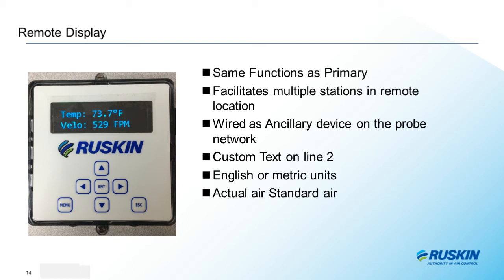Two lines of the display can be configured. Actually, line 2 of the display can be configured with custom text, such that where it says VELO in this screen shown here, you can edit that and have it read AHU1 or RTU3 or any custom text you want to see. Configuration options support both metric and English units and can be set to display either actual airflow or standard airflow, adjusting for both altitude and humidity when standard air measurement is required.